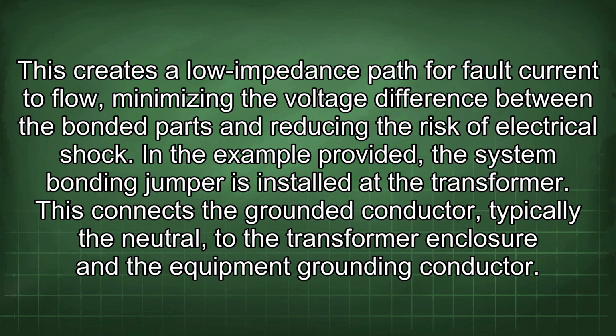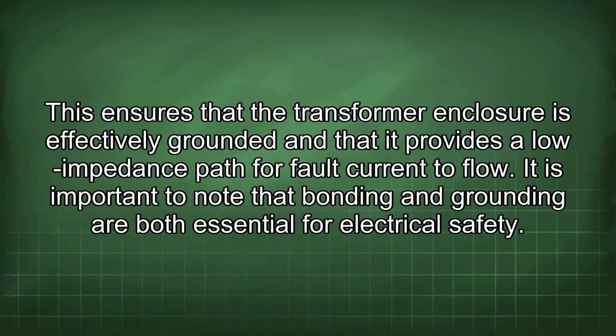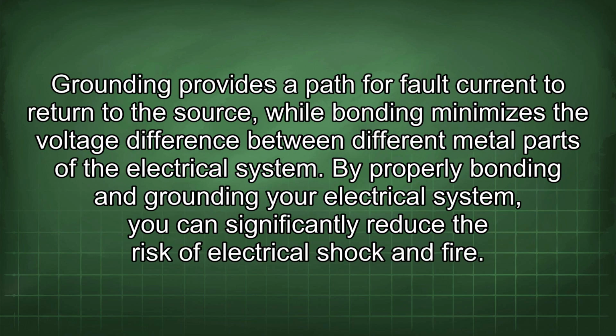In the example provided, the system bonding jumper is installed at the transformer. This connects the grounded conductor, typically the neutral, to the transformer enclosure and the equipment grounding conductor. This ensures that the transformer enclosure is effectively grounded and that it provides a lower impedance path for fault current to flow. It is important to note that bonding and grounding are both essential for electrical safety. Grounding provides a path for fault current to return to the source, while bonding minimizes the voltage difference between different metal parts of the electrical system. By properly bonding and grounding your electrical system, you can significantly reduce the risk of electrical shock and fire.